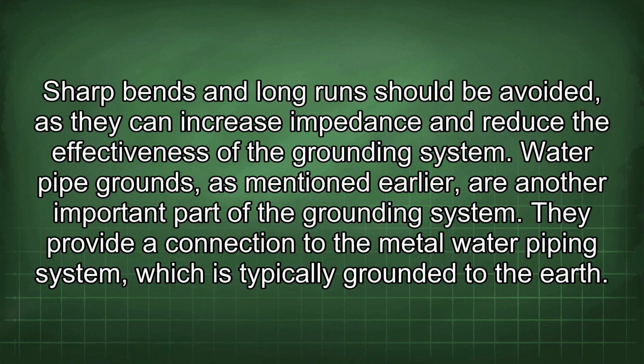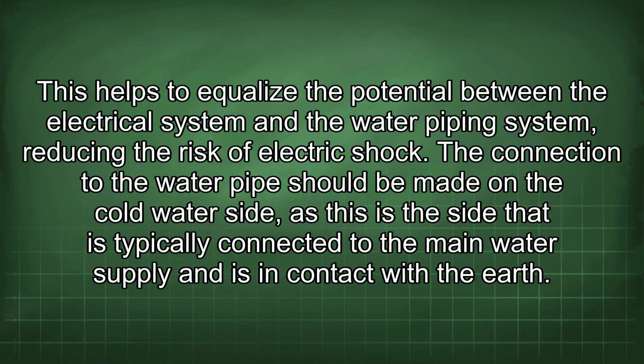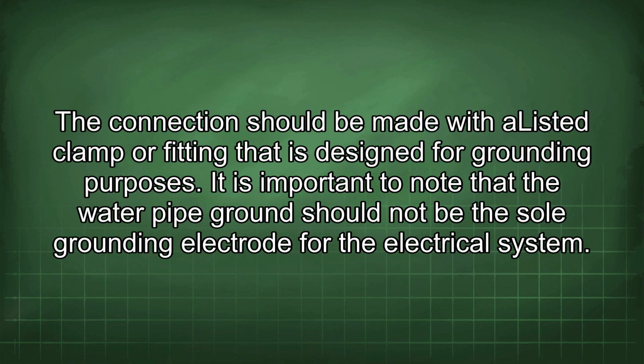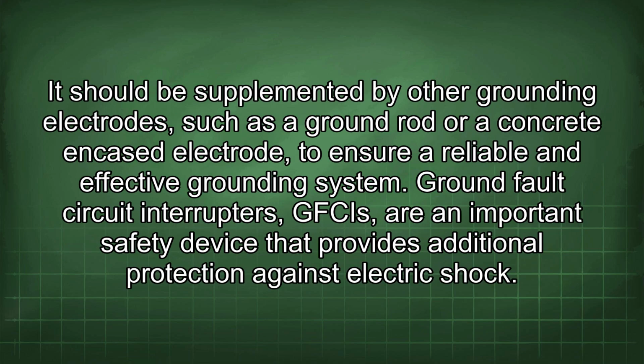They provide a connection to the metal water piping system, which is typically grounded to the earth. This helps to equalize the potential between the electrical system and the water piping system, reducing the risk of electric shock. The connection to the water pipe should be made on the cold water side, as this is the side that is typically connected to the main water supply and is in contact with the earth. The connection should be made with a listed clamp or fitting that is designed for grounding purposes. It is important to note that the water pipe ground should not be the sole grounding electrode for the electrical system. It should be supplemented by other grounding electrodes, such as a ground rod or a concrete encased electrode, to ensure a reliable and effective grounding system.